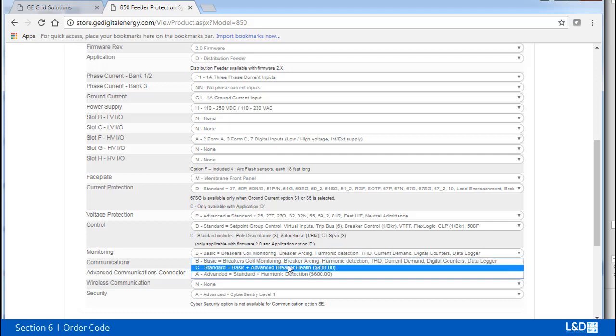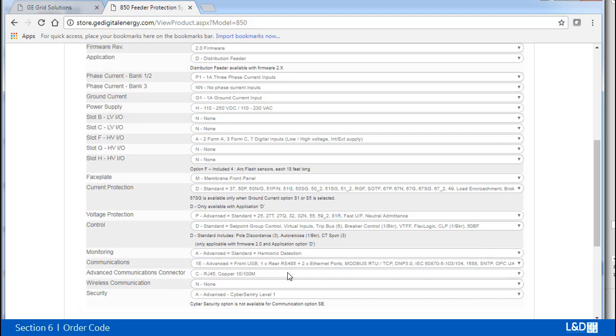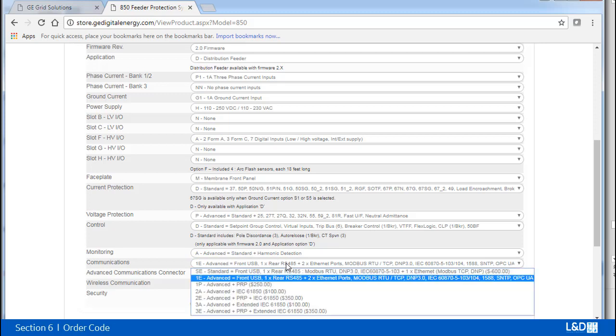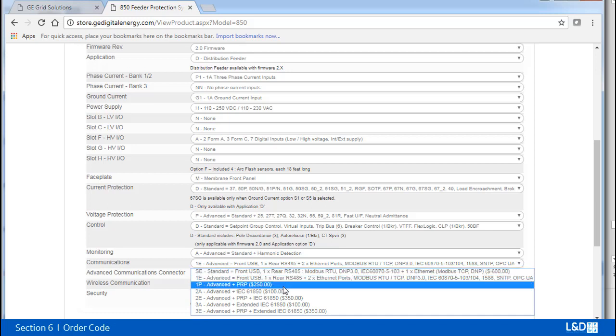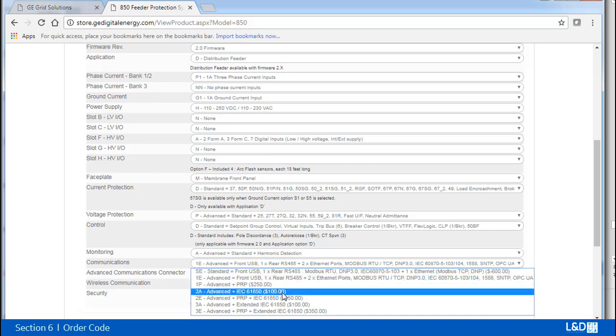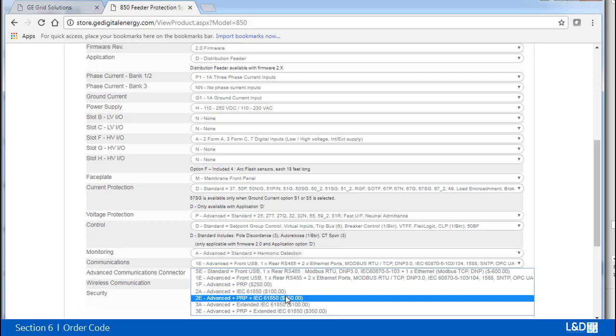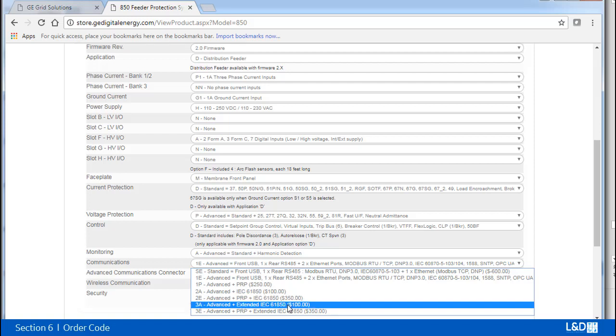And then for monitoring, we can choose basic, standard, or advanced. And communication, most important if you want to have 61850, you need to choose at least 2A. Usually we have PRP with 61850, that's 2E. Then you get extended 3A and 3E.